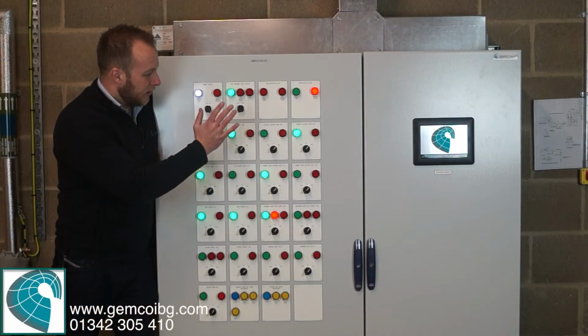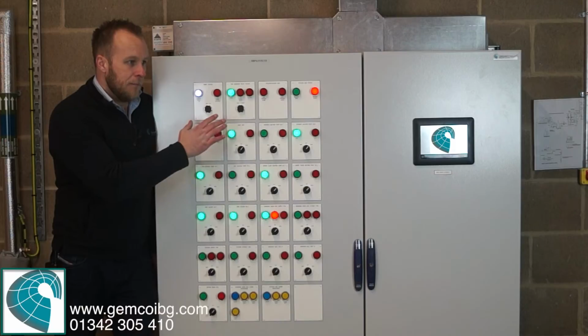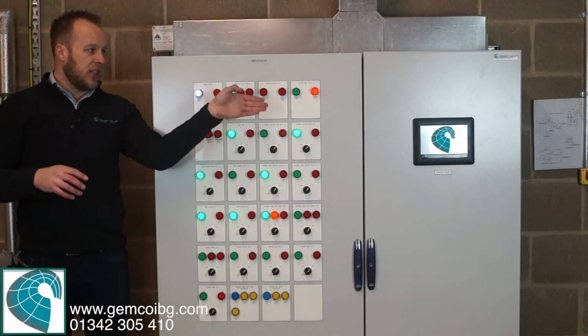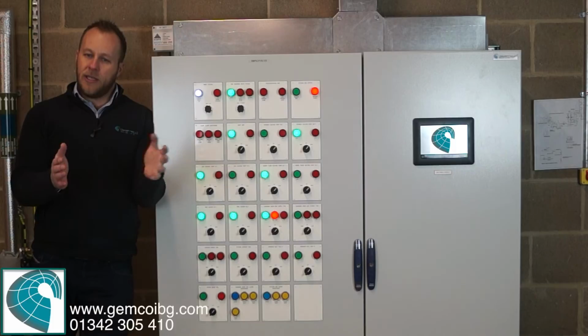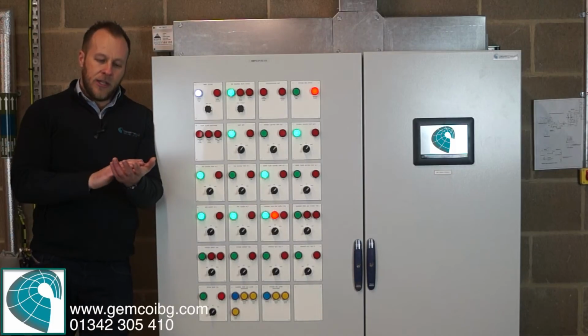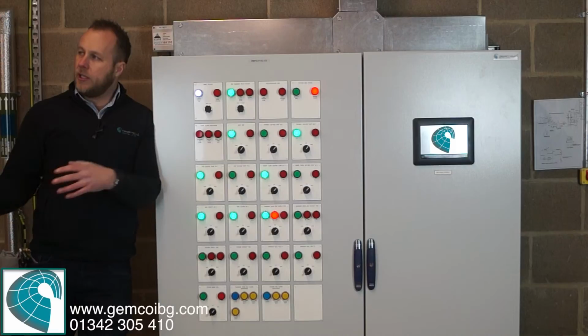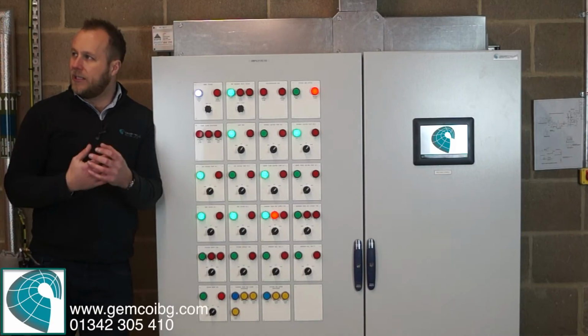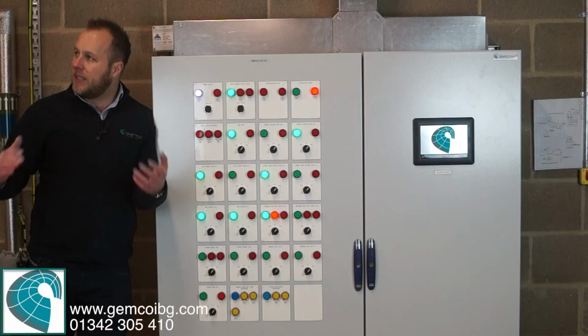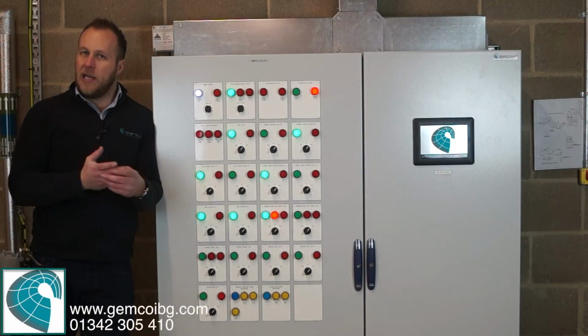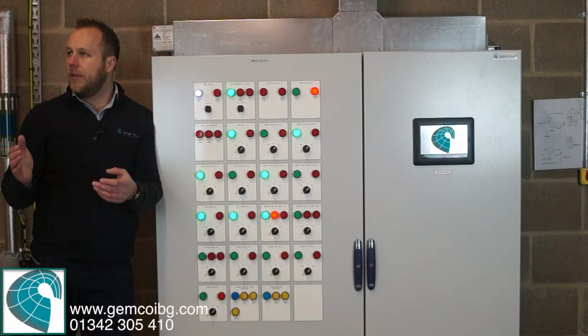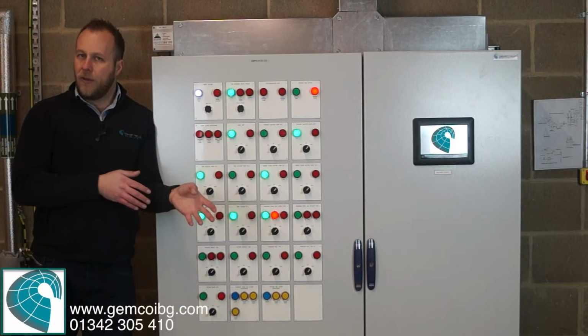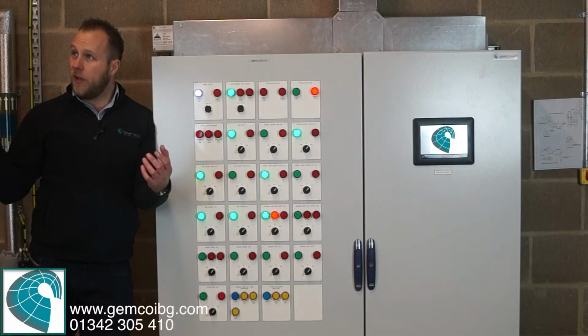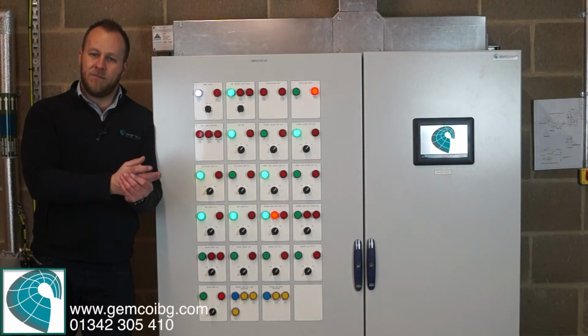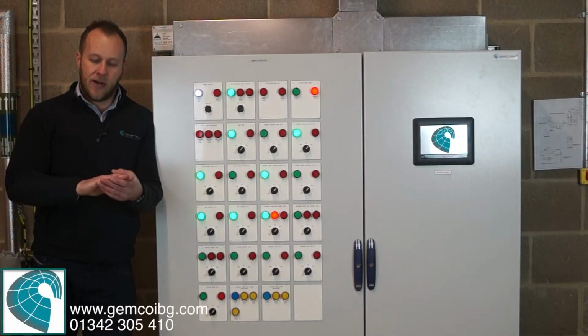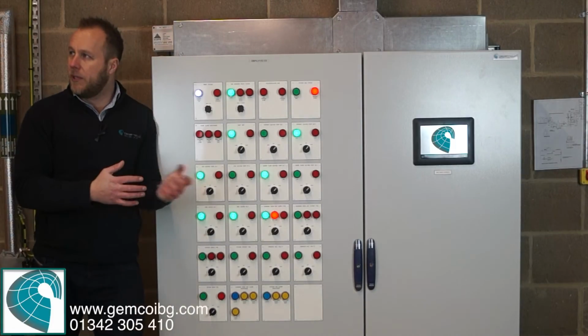And the last thing to mention on that is the optimization. Although you've got a time zone, say your time zone's set to 8 o'clock in the morning, that's when you're going to come in, that's when you want the heating on. The optimizer will look at the outside air temperature and the inside temperature, and it will calculate how long it needs to come on in order to be up to temperature for the start of occupancy. Now we've put a limit on that of an hour, so it won't ever come on more than an hour before, based on this application. You've got good thermal properties in the building, and the system isn't that big, so we've limited it to an hour, but you may find that plant comes on just a little bit earlier.